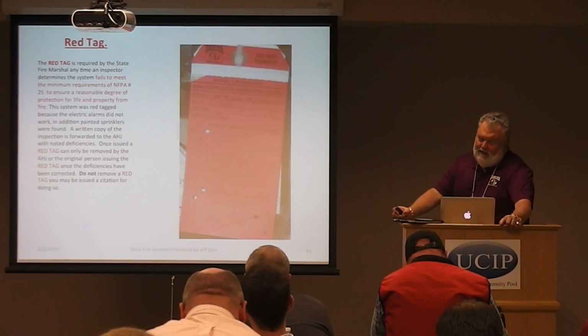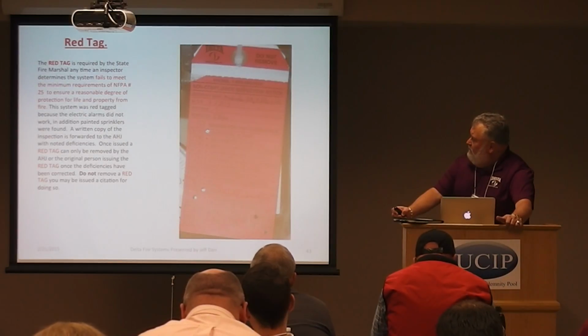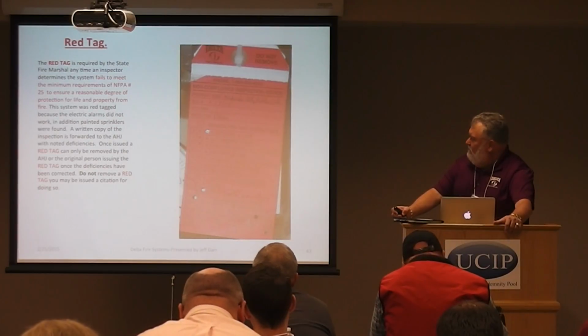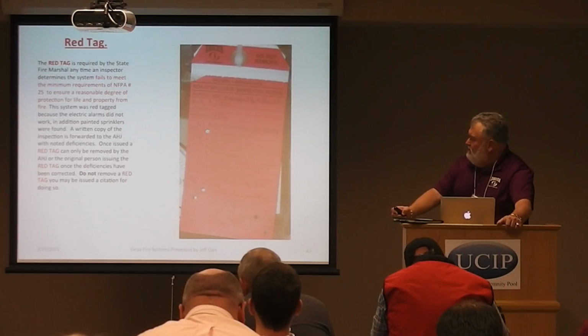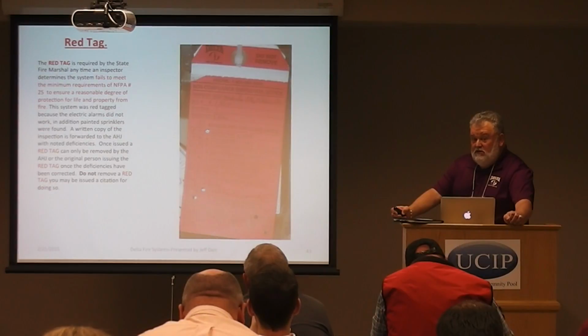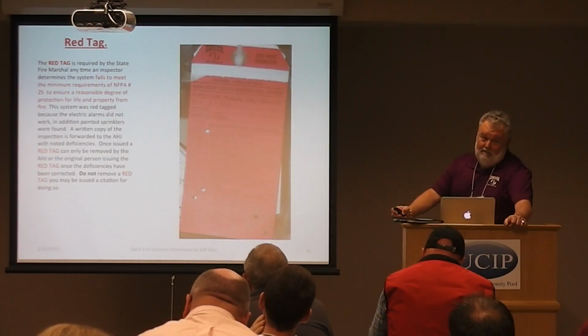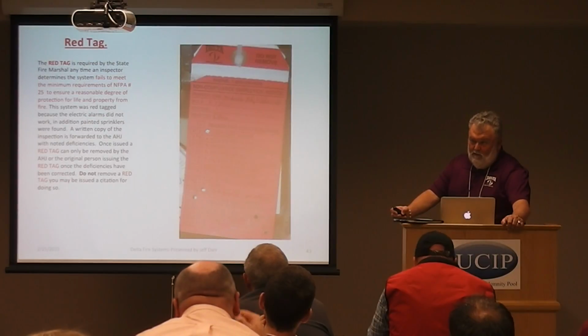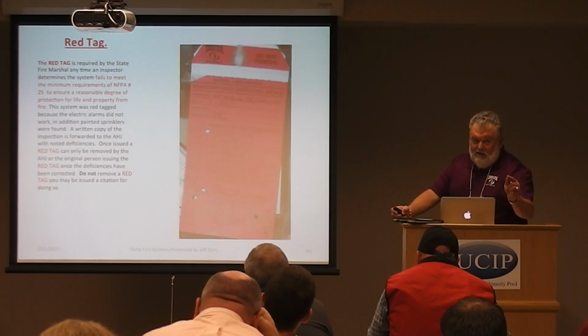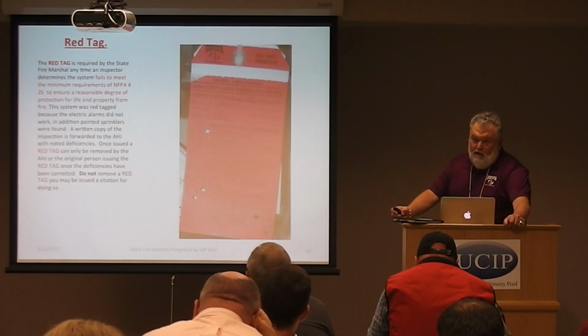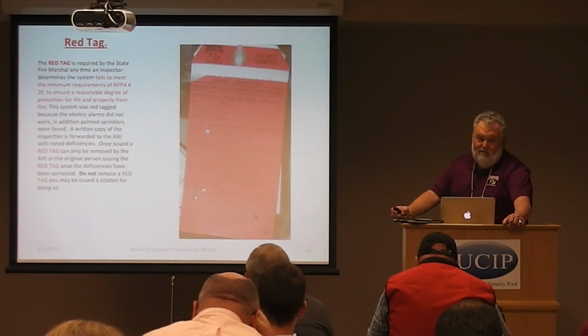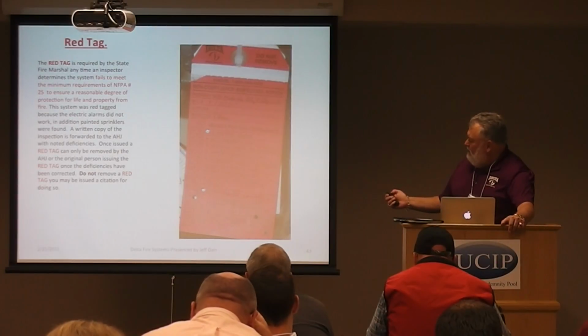This is what we call the red tag system, and this is required by the state when we find that a system fails to meet the minimum requirements of NFPA 25 to ensure a reasonable degree of protection for life and property. Once an inspector places this tag, you as an owner cannot remove it. There's only 2 people that can remove that tag once he places it: either himself or the fire official. The fire marshals tell me that they have issued fines for owners removing this tag. Don't do it.